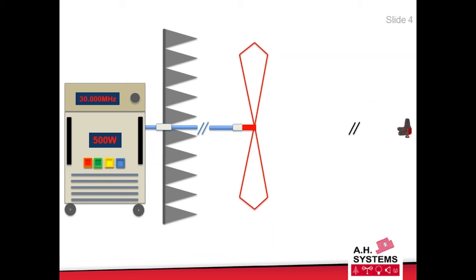The reason it's there is you can get a far more predictable result if you're fault finding a test chamber setup by monitoring the boresight field strength rather than trying to take some point elsewhere in the calibration plane. In fact, you'll find the boresight is not a point on the calibration plane, but I would strongly recommend, if you are faulting the system, to put it on the boresight. You can calculate what it should be approximately, and it will be very consistent rather than taking the variations that go with field strength across the calibration plane.